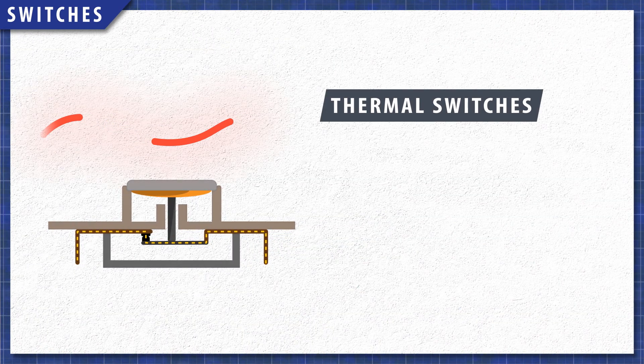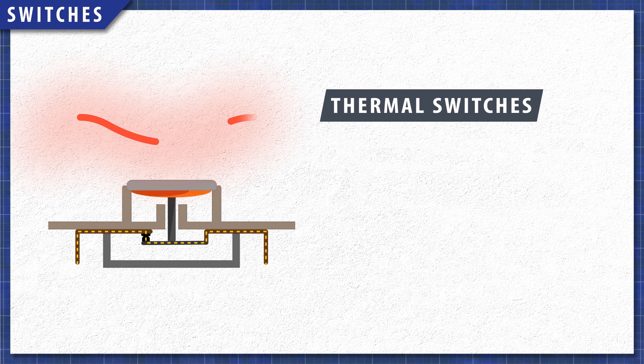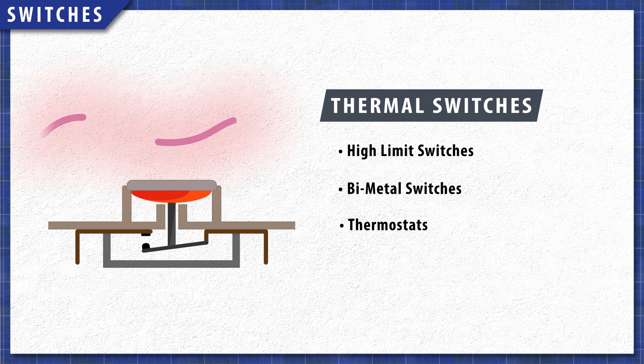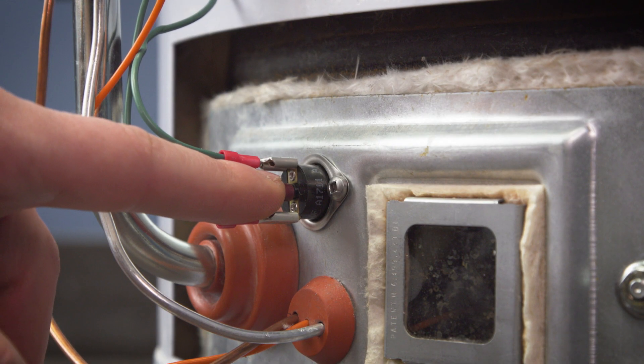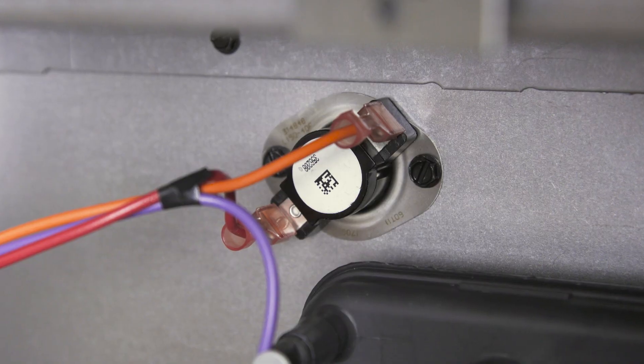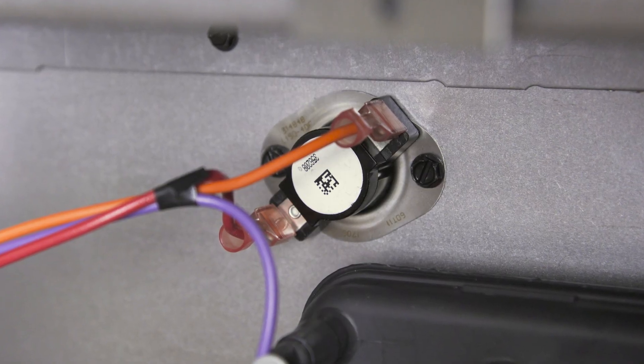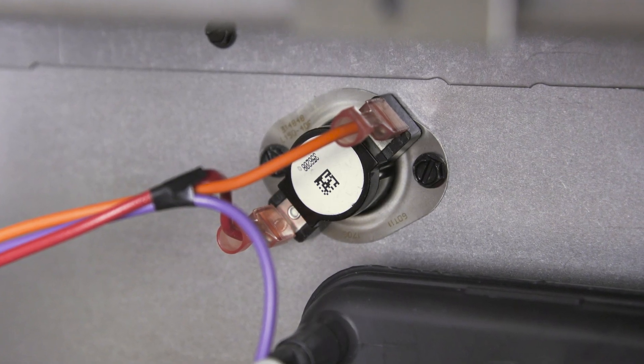Thermal switches respond to heat and will disconnect power at a set temperature. In some cases these are called high limit switches, bimetal switches, or thermostats. Some switches will reset automatically and others will use a reset button. These are commonly found in furnaces, dryers, and water heaters.